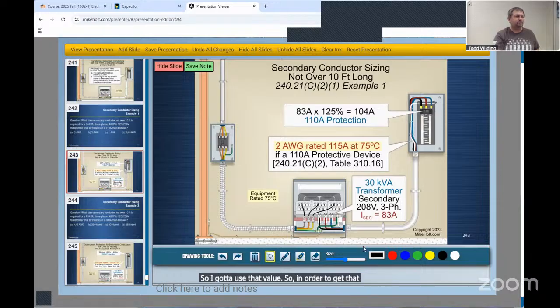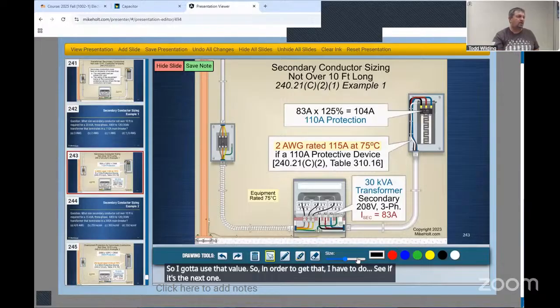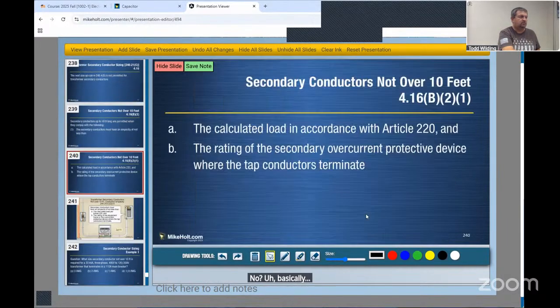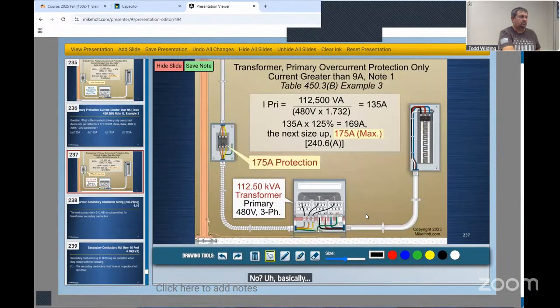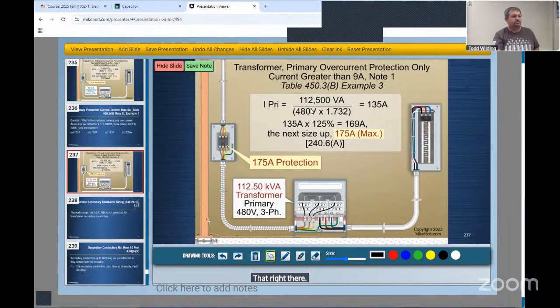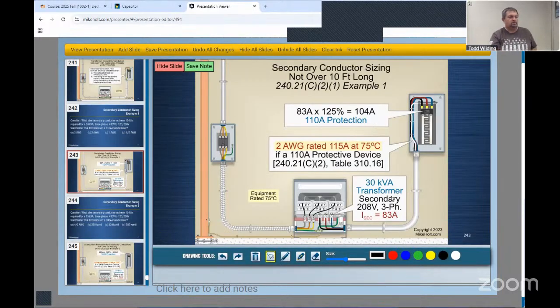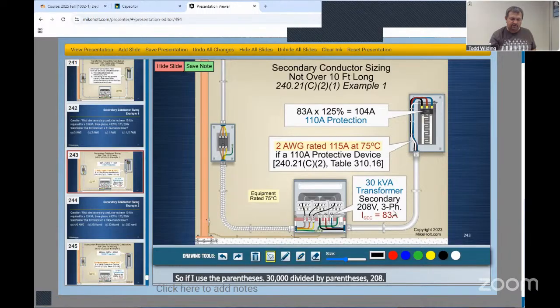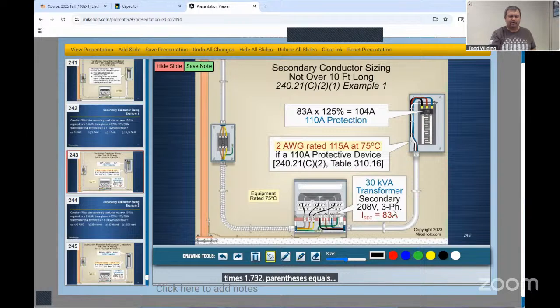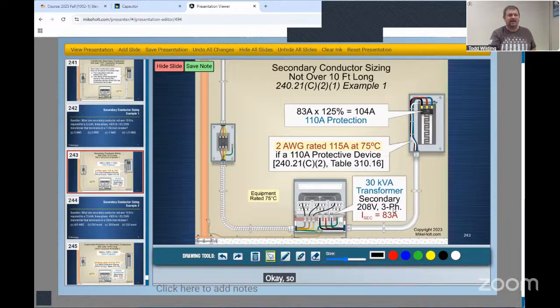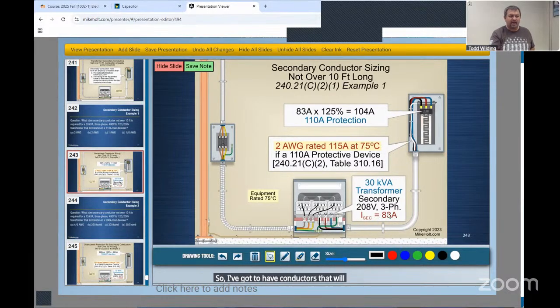So in order to get that, I have to do, see if it's the next one. No. Basically, that right there. But I'll use 208 and the 1.732. So I can go 30,000 divided by 208 divided by 1.732. So if I use the parentheses, 30,000 divided by parentheses 208 times 1.732 parentheses equals 83.274. Okay, so don't forget that square root of 3, 1.732. So I've got to have conductors that will carry 83 amps.